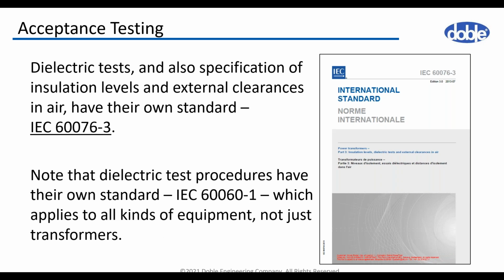The situation with the dielectric test is a little bit more complex. The general definitions and test methods are explained in IEC 60060 Part 1, but this standard is common for all kinds of equipment. On the other hand, the dielectric tests include insulation level and external clearances for power transformers in particular. They have their own standard, which is IEC 76 Part 3.